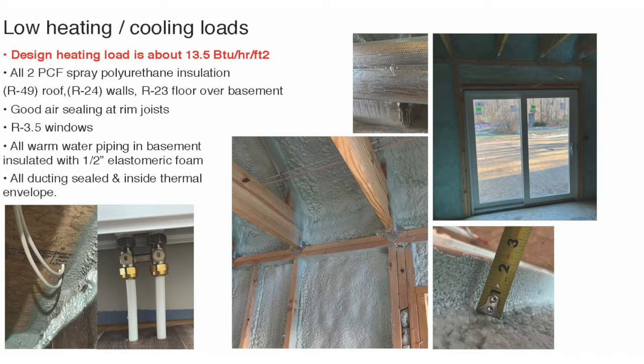So here's some of the stats on it. The design heating load worked out about 13.5 BTUs per square foot per hour, which, you know, again, that 10 to 15 BTU per square foot per hour range is very achievable today. I know we were talking, I think Gary talked about a project was even less than that, maybe 6 BTUs per square foot per hour. Again, everything was spray foam.